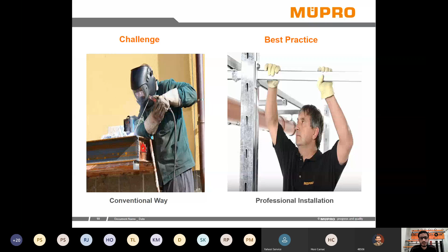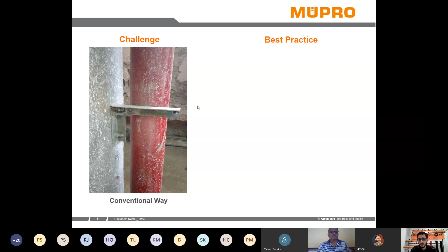Now let us see another challenge which we face during installation of pipe supports. Here a firefighting riser is to be installed, and look at the amount of supporting which is required. Two angles have to be welded first, then painted, then two anchors are required. Apart from that, a U-bolt is required, and when you clamp any pipe with a U-bolt, the only grip you get is the line contact of the U-bolt with the pipe, and it is only a grip of 180 degrees, not more than that. So let us see now how we can make this same support more engineered and better in a modular way.